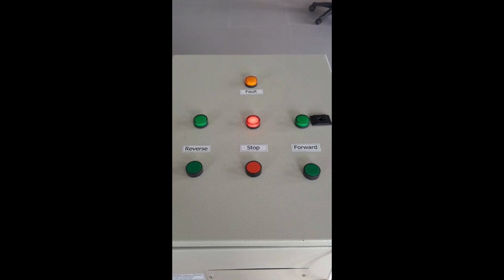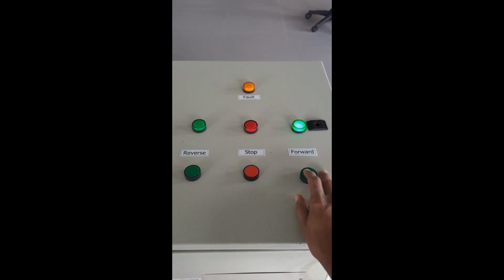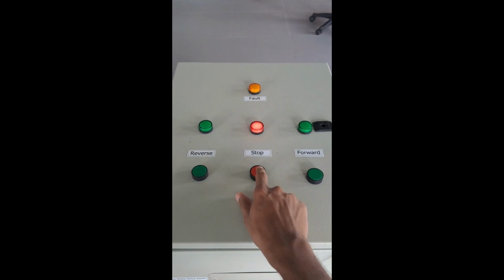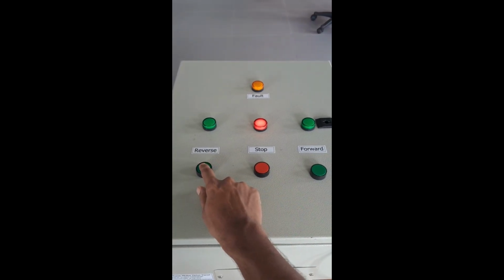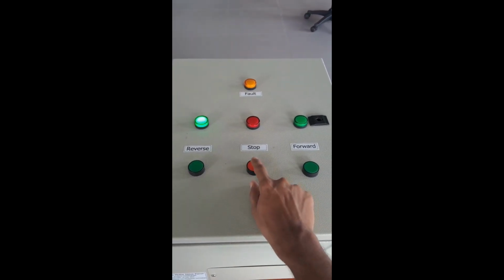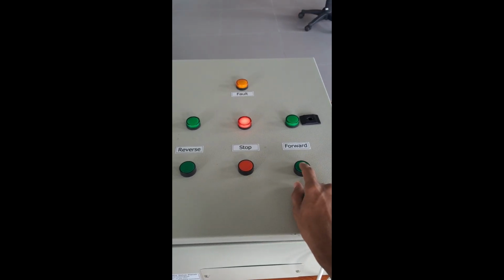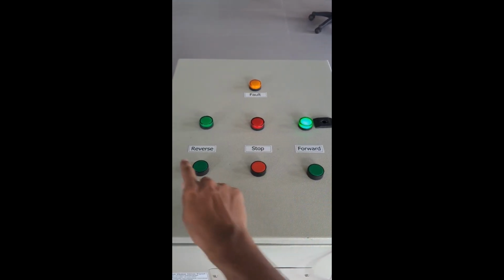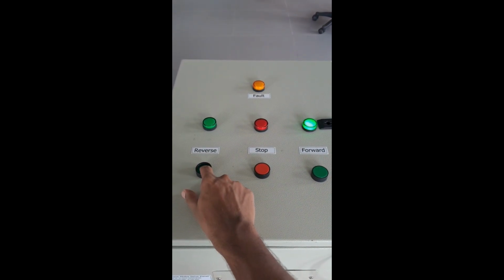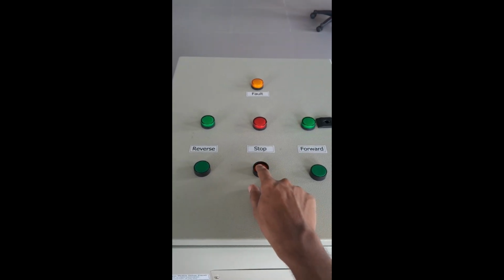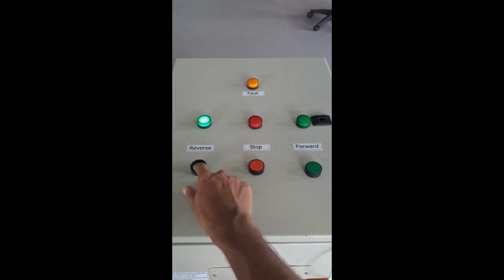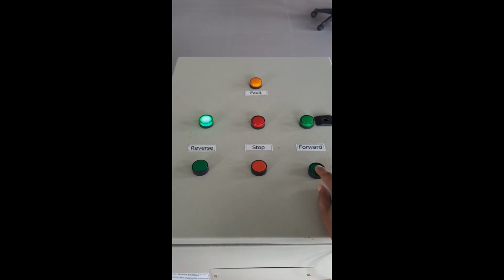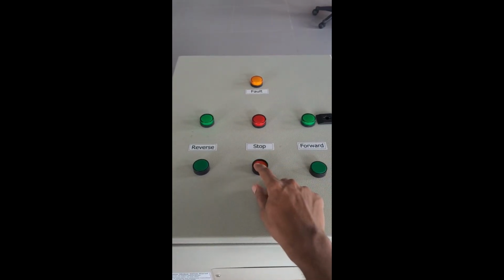First, when we press the forward button, it will go forward, and we have to stop the motor, then go to reverse, and then go back to stop. So it is not allowed to reverse run when forward is running. The only thing is you have to stop it and go to the other direction.